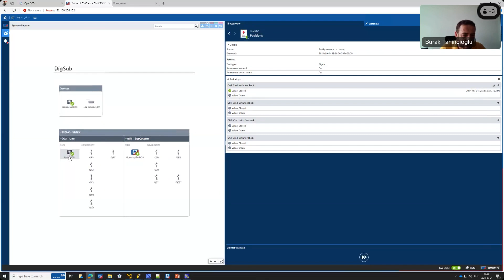So I'm coming to the end, and the last test case is for the physical IED. This was for the bus coupler IED signals, gateway signals, and that would be also one for the positions of the line bay. I will clear this test - you will see that I will have a closed-open cycle for all this.